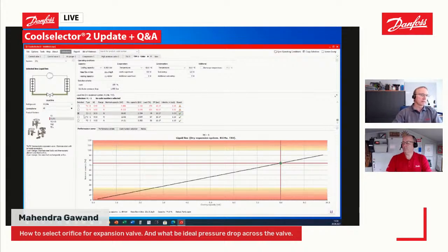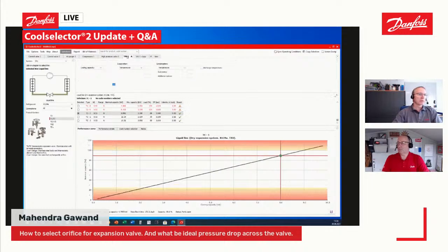In the summer condition here, it would be a TC orifice 1 with a 74% load. In winter condition, the temperature, and by that the inlet pressure, is much lower, but here we can see that it still fits. So this would be the choice in this case. 89% is okay.